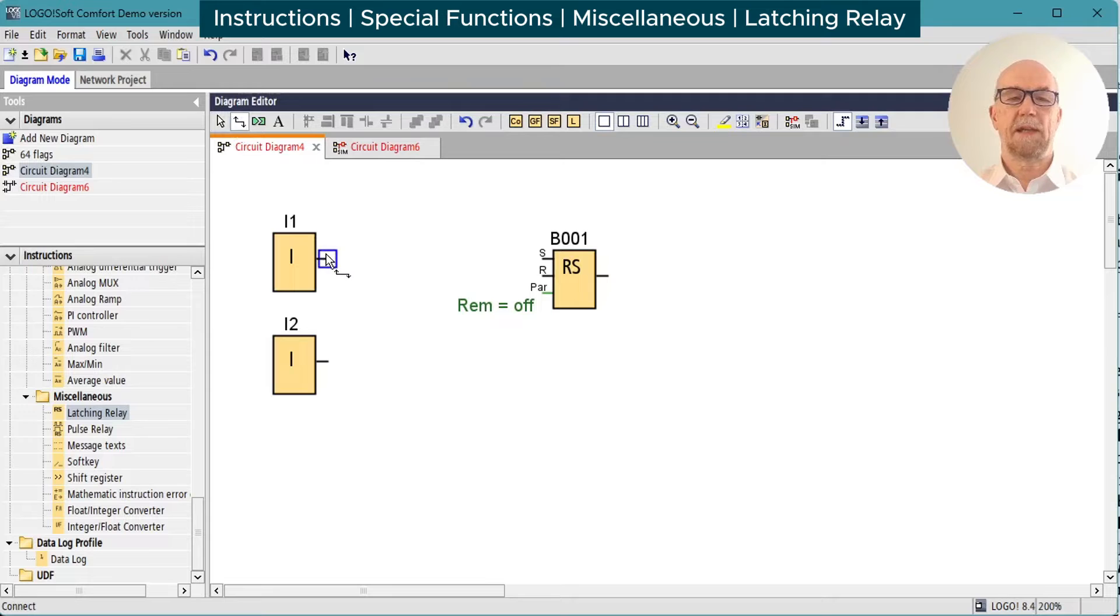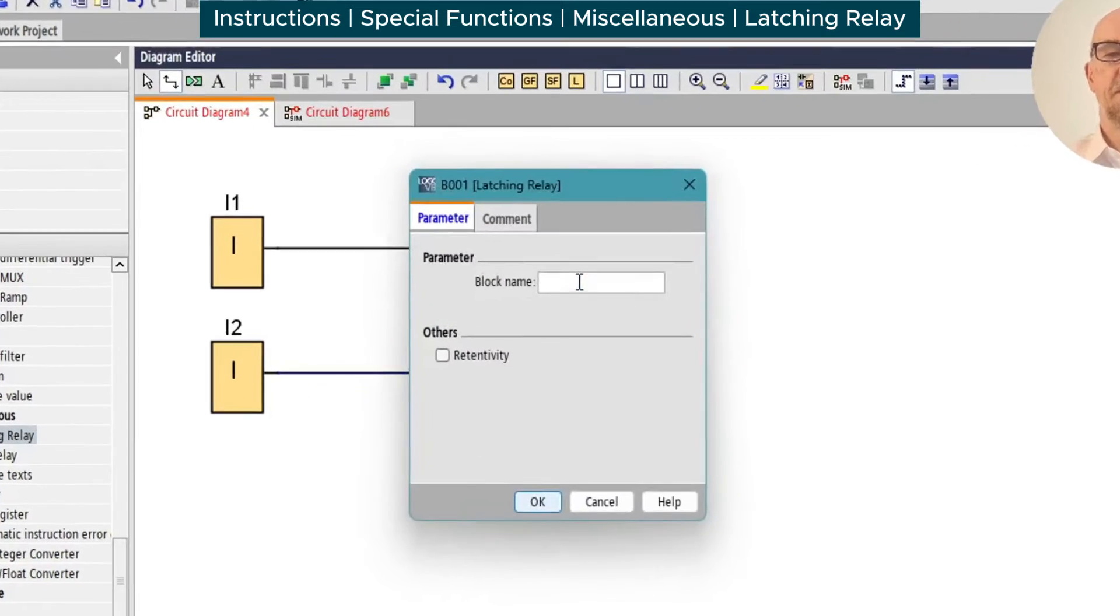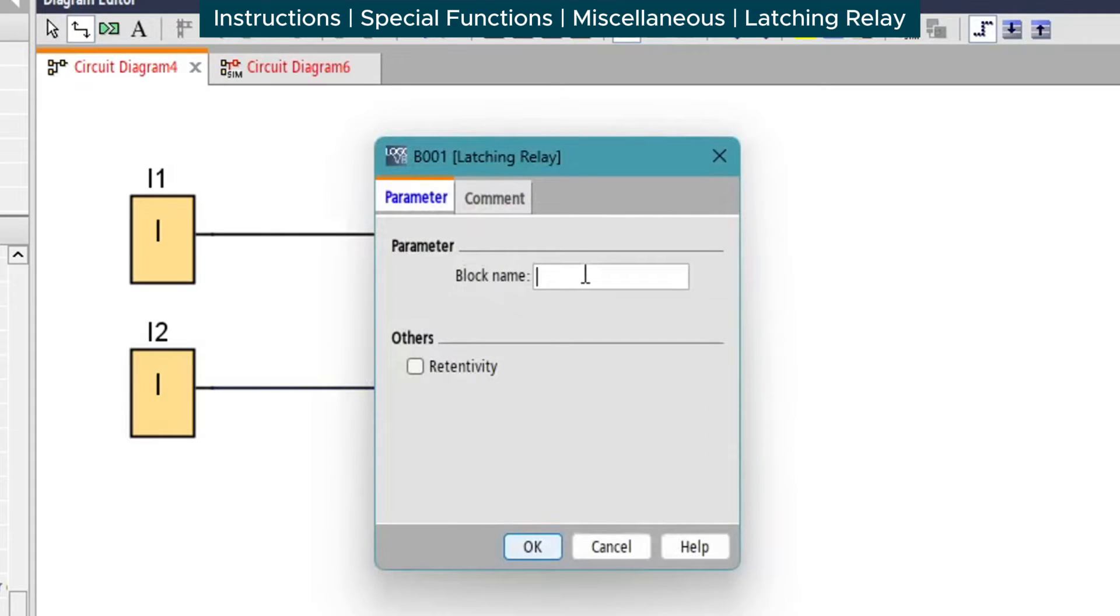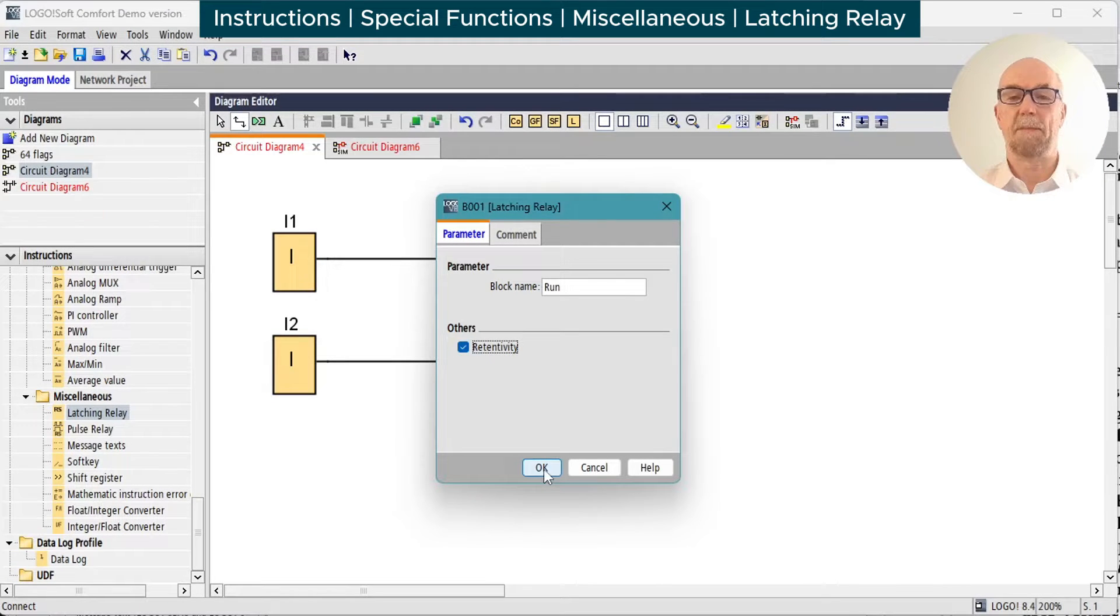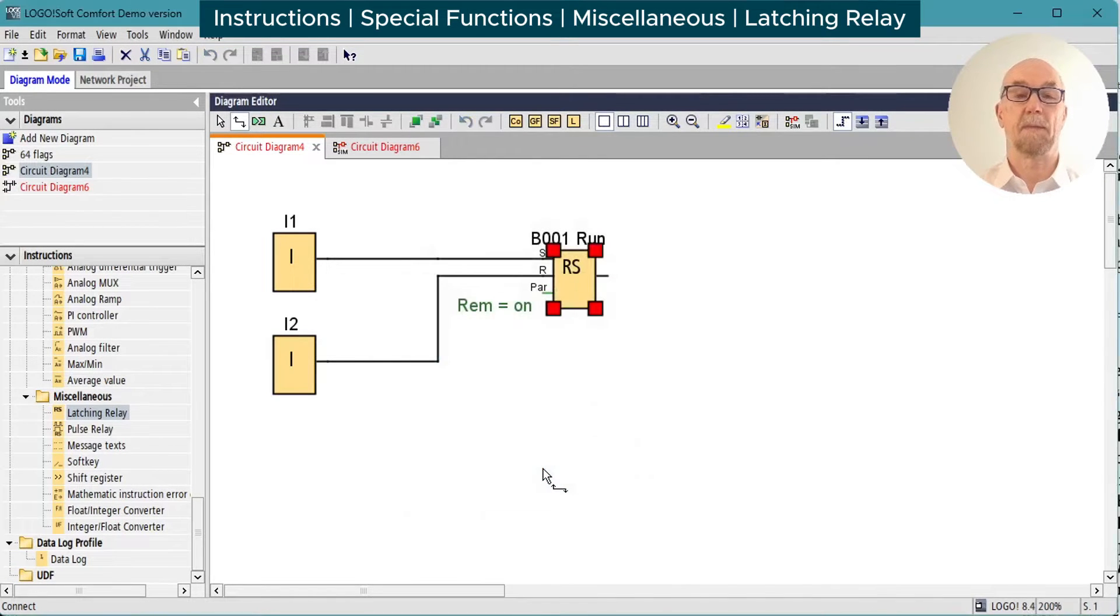The LOGO latching relay is a set-reset type and works very simply. Very little to set up other than give it a name and decide whether you want it retentive or not. We'll set retentivity on, which means that during a power cycle it will remember its status on power up.